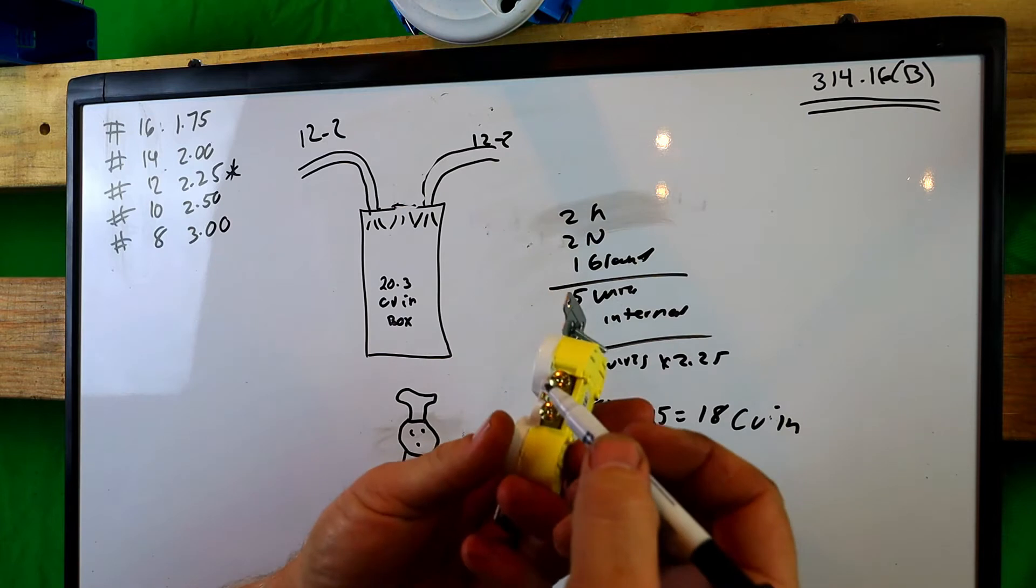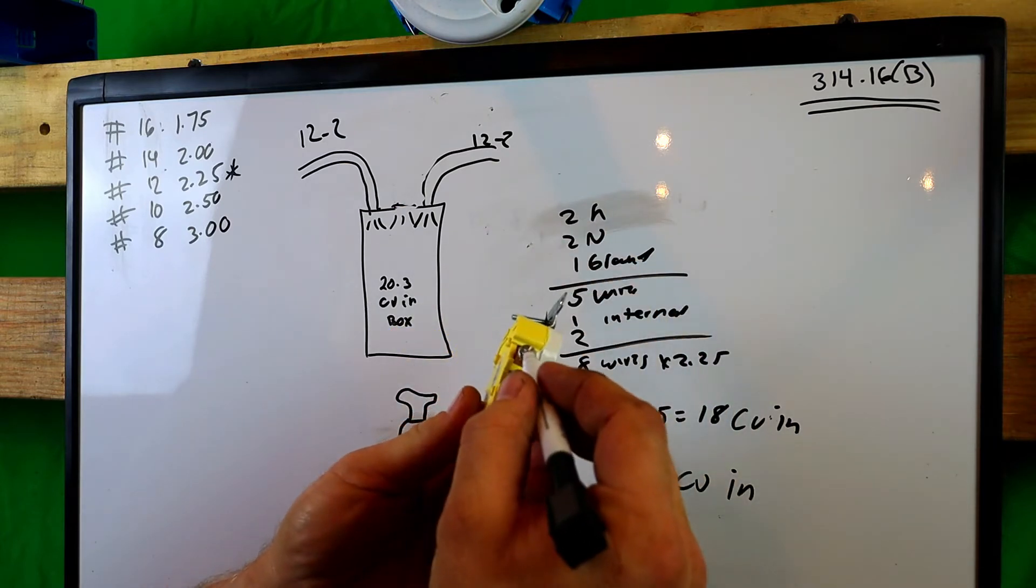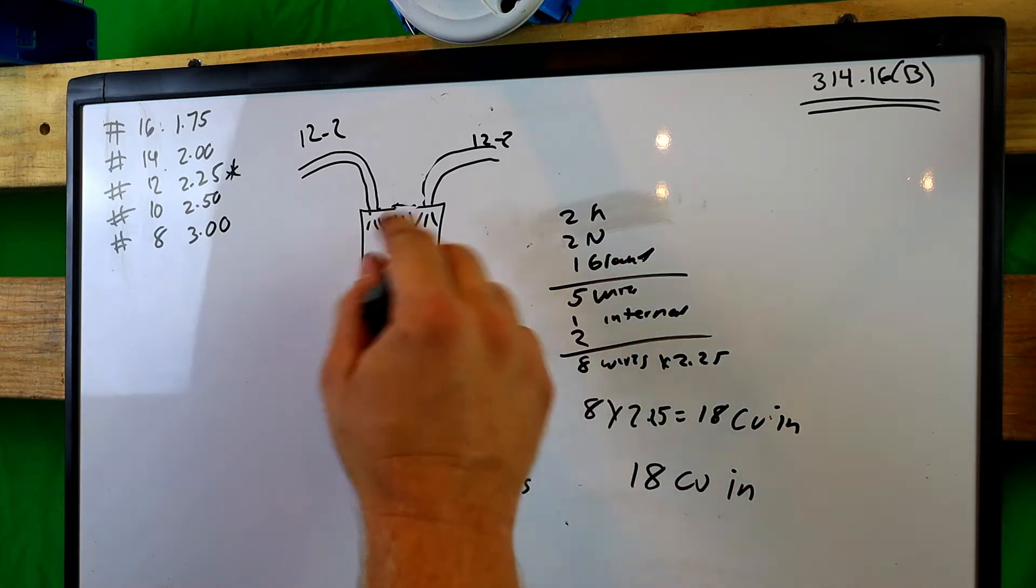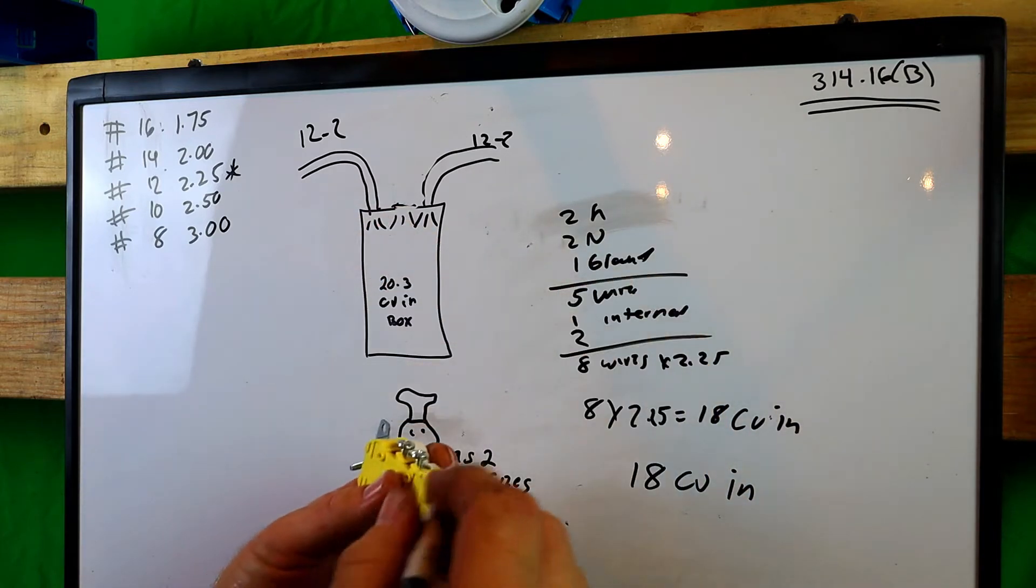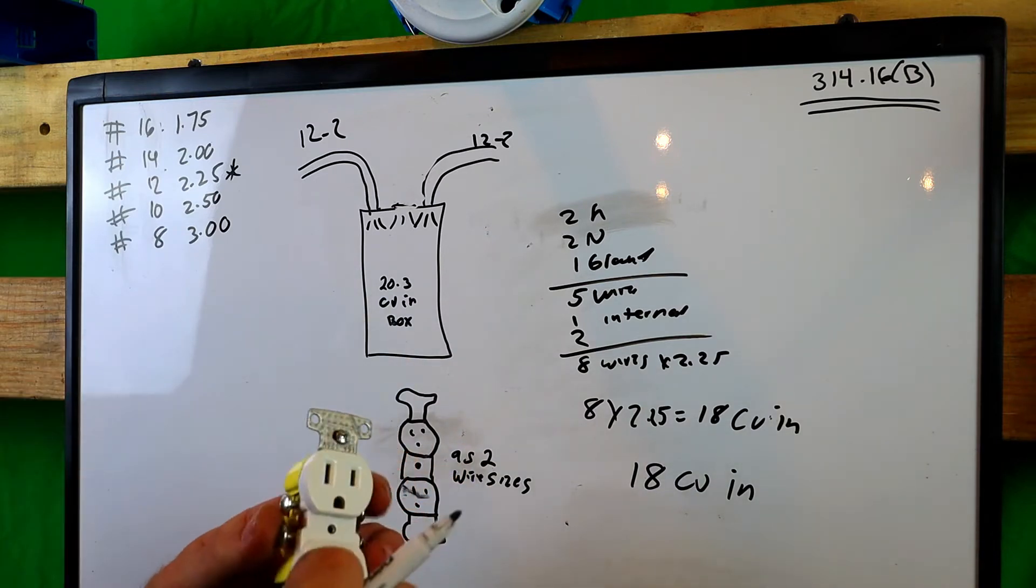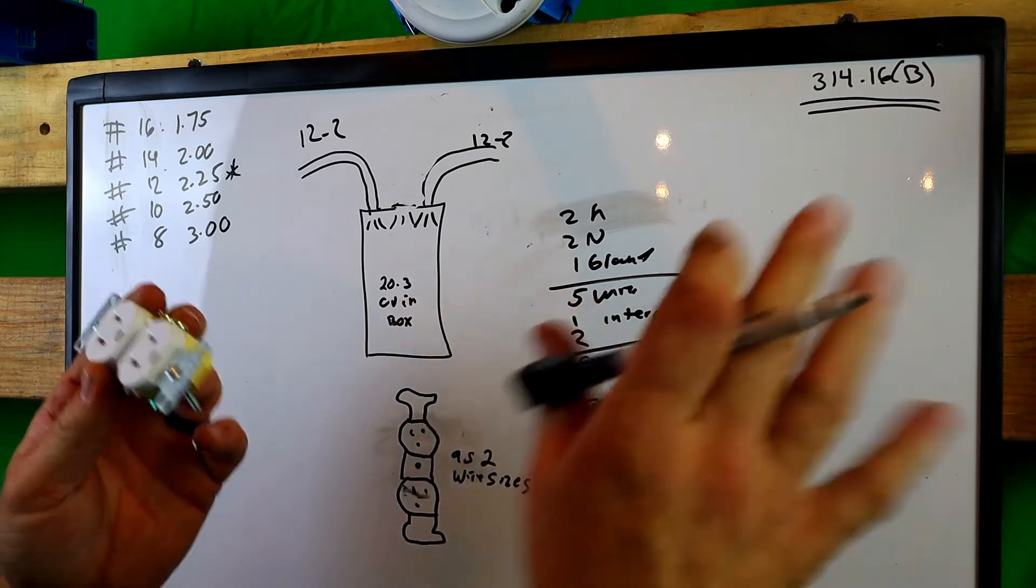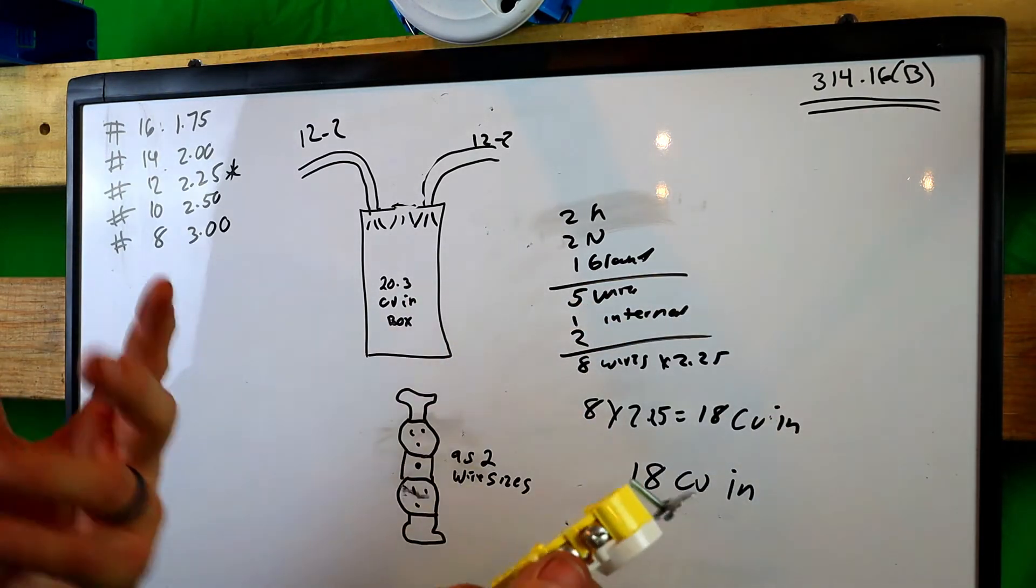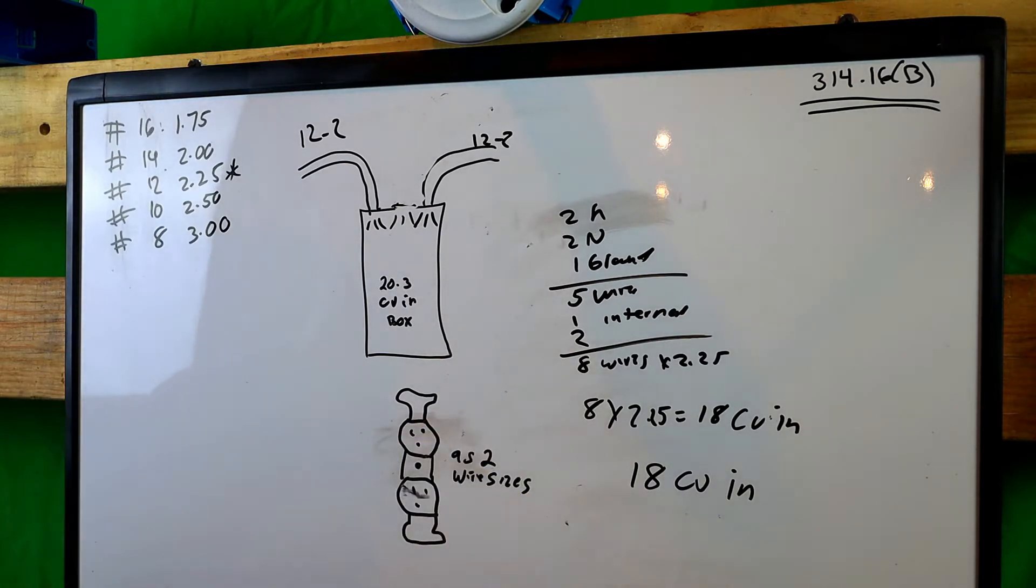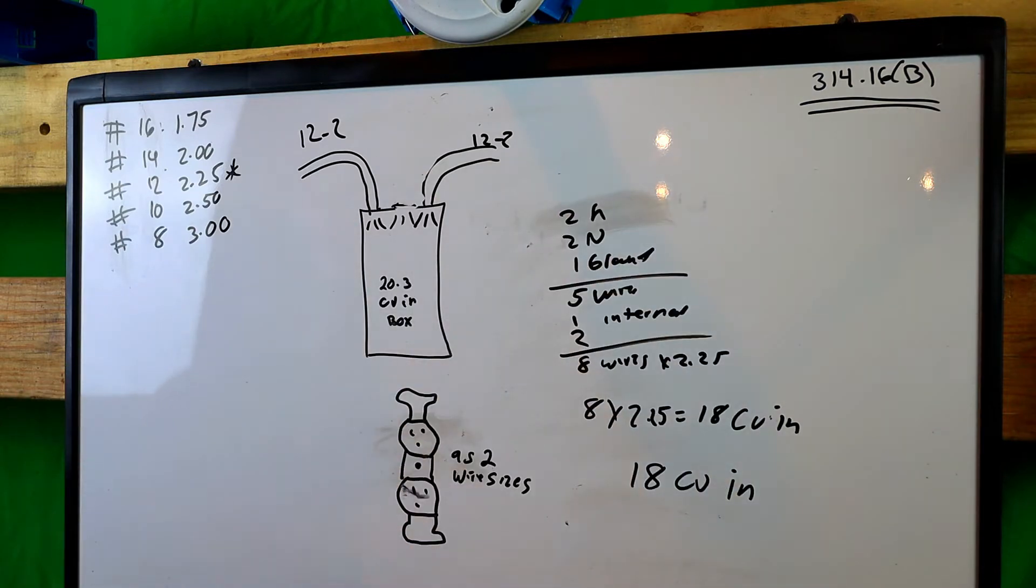All right. So with the receptacle, what you can do with these two 12-2s, you can actually put one hot here, one hot here, because there's two hots, and one neutral there and one neutral there, because there's two neutrals, and then one ground there. You got to make a pigtail on that ground, obviously. And you can do that way. Now, I don't like doing that. Simple fact that if this receptacle goes bad, you know, it's going to take out the rest of your circuits. Now, is that a big deal on a house? No. Is it quick and easy? Yes. Does it look like crap? I think so personally, but it's up to you. You're the be the one wiring your house or whatever you're wiring. So make your own assumption on that. And we'll go from there.